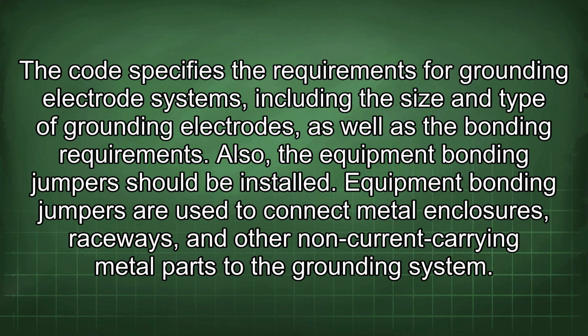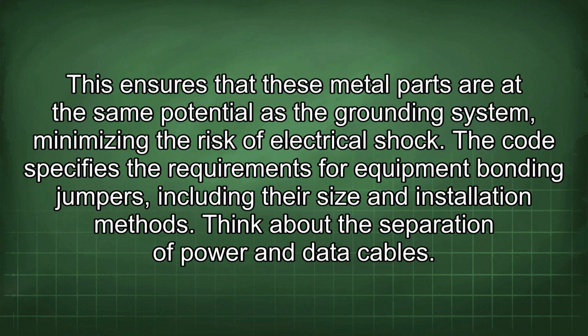Equipment bonding jumpers are used to connect metal enclosures, raceways, and other non-current carrying metal parts to the grounding system. This ensures that these metal parts are at the same potential as the grounding system, minimizing the risk of electrical shock. The code specifies the requirements for equipment bonding jumpers, including their size and installation methods.